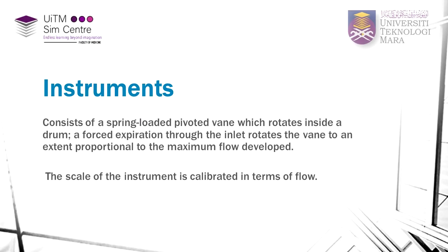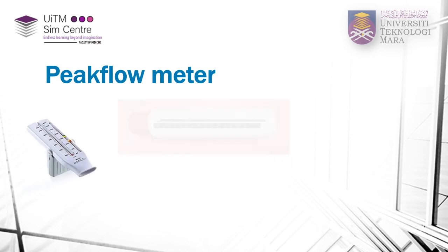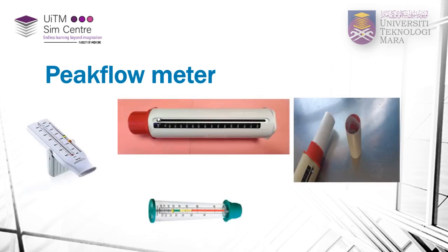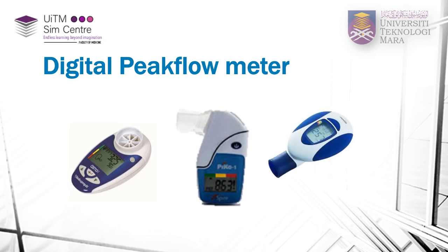What is a peak flow meter? A peak flow meter consists of a spring-loaded, pivoted vane which rotates inside a drum. A forced expiration through the inlet rotates the vane to an extent proportional to the maximal flow developed. The scale of the instrument is calibrated in terms of flow. These are the peak flow meters that are commonly used, and these are the digital peak flow meters.